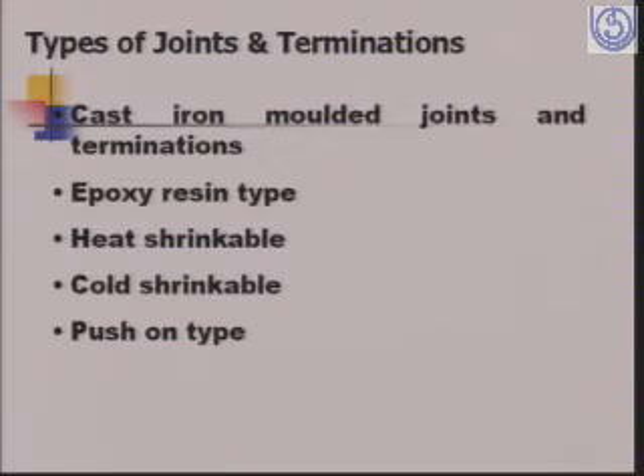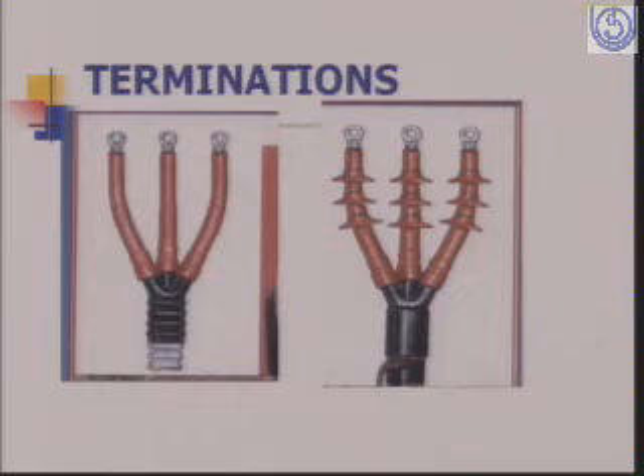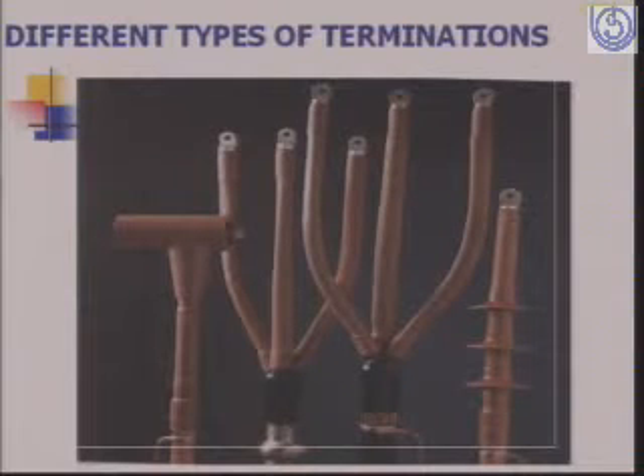Earlier we were using cast iron molded joints and terminations, which are now obsolete. The new types are the epoxy resin type, the heat shrinkable type, the cold shrinkable, and push-on type. With these cold shrinkable and push-on types, you have to hardly do anything, and they get clamped to the cable in the cold or ambient temperature conditions. These are the various terminations. You can see this is one type of termination which I have shown. Then this is another type of termination which can be used.